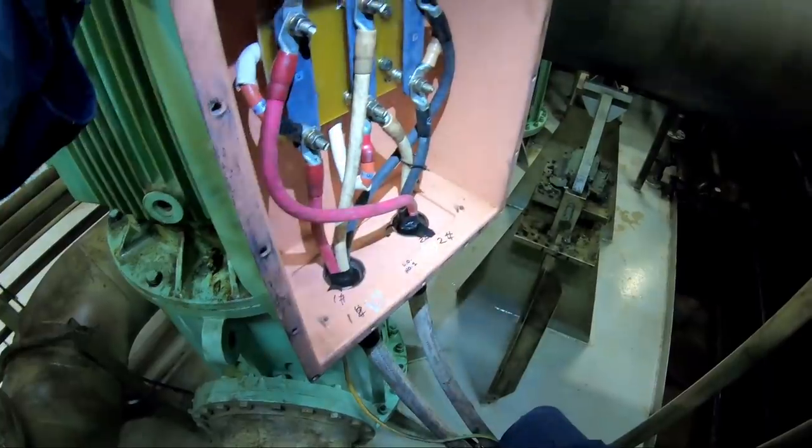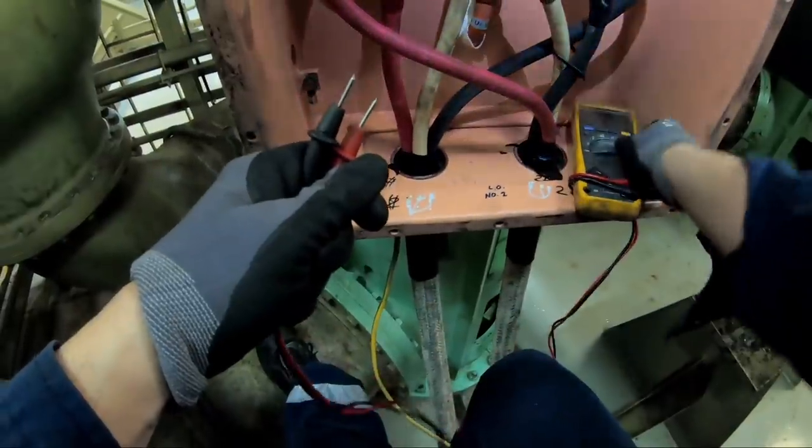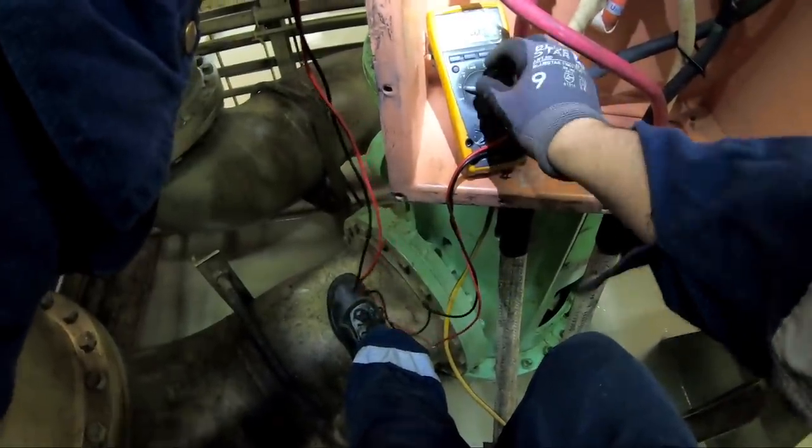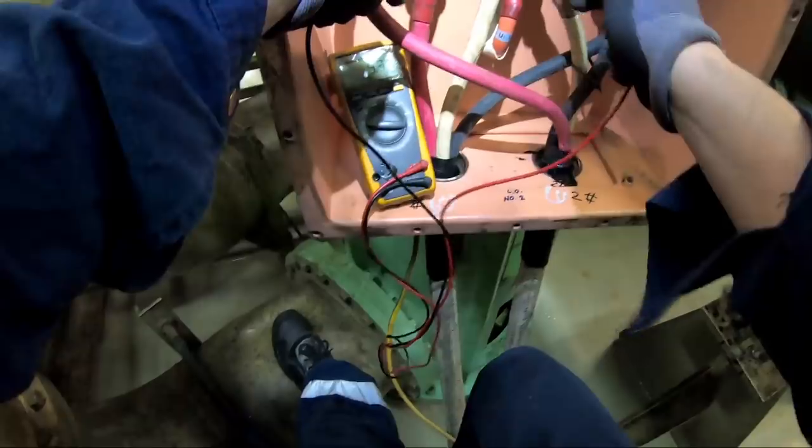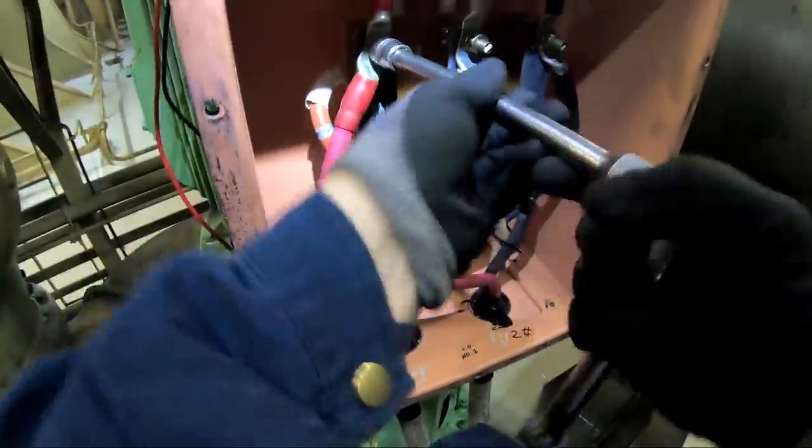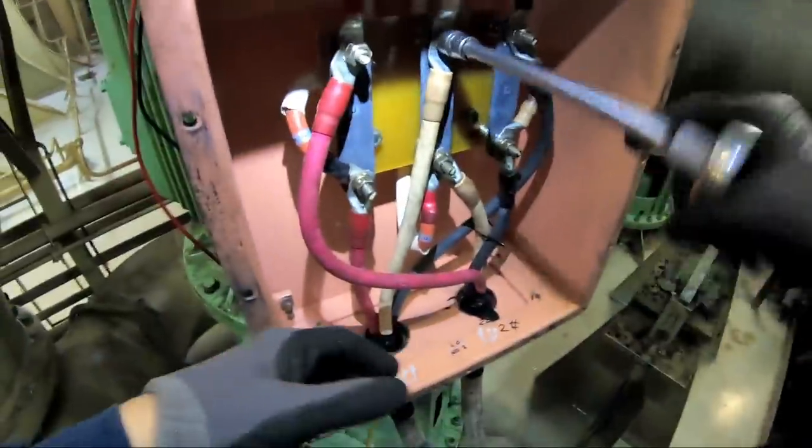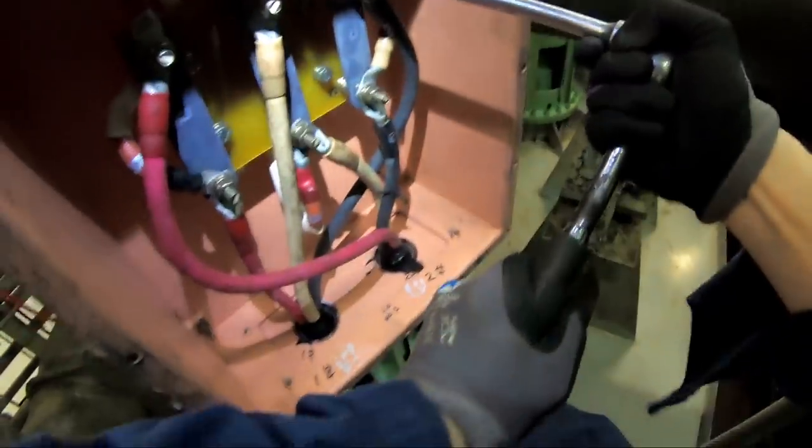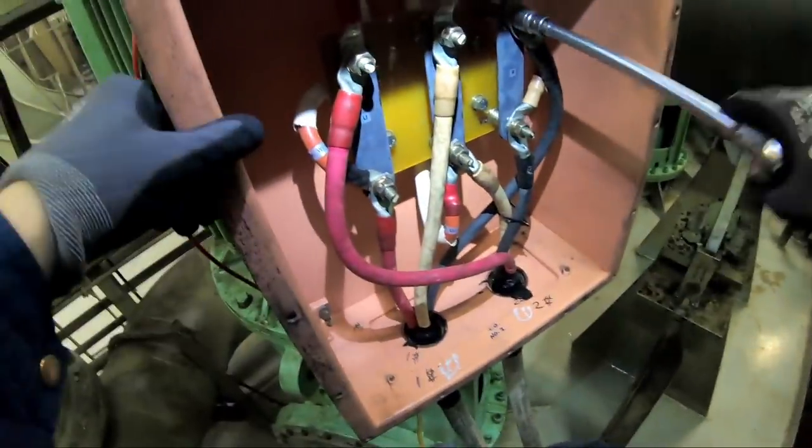Visually speaking, there is no sign of any abnormalities on the connection of the motor. As a safety reminder, before touching anything we need to test if the line is live or not, if you have 440 supply or not. After confirming that it is really a dead circuit, then I have decided to remove all the connections coming from our control panel side. This is to isolate the motor completely and check the winding conditions.